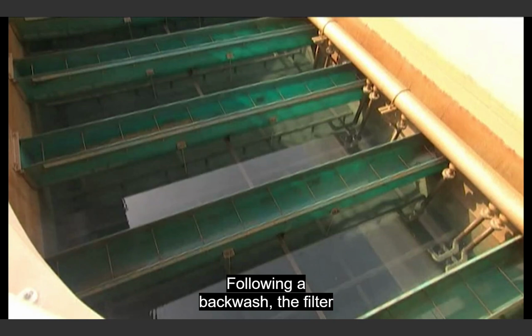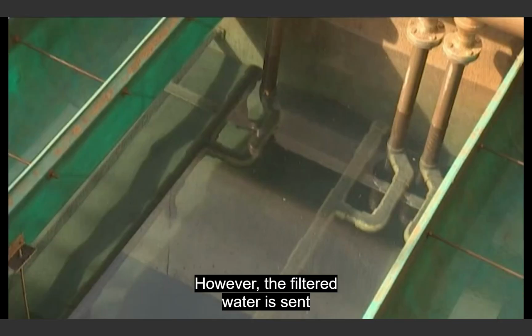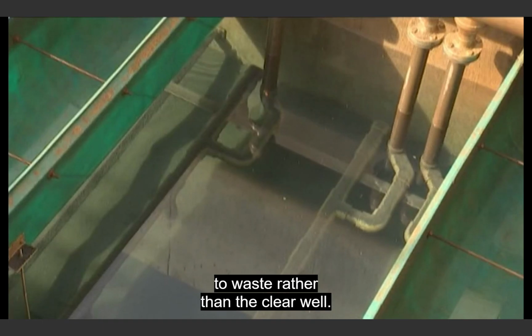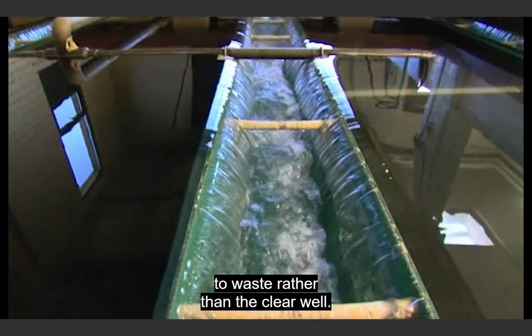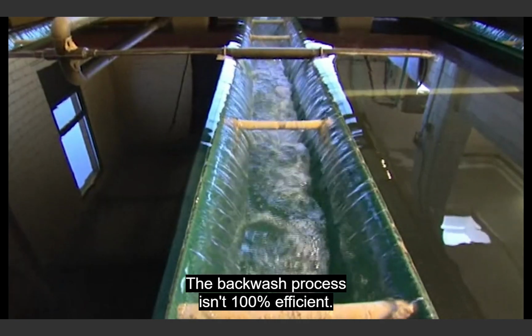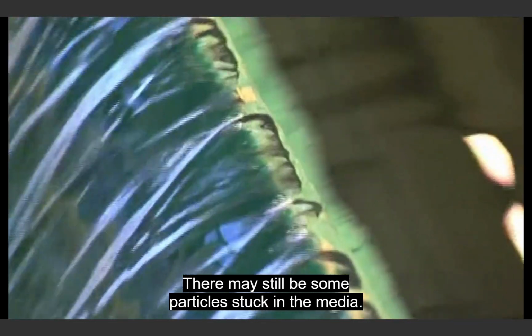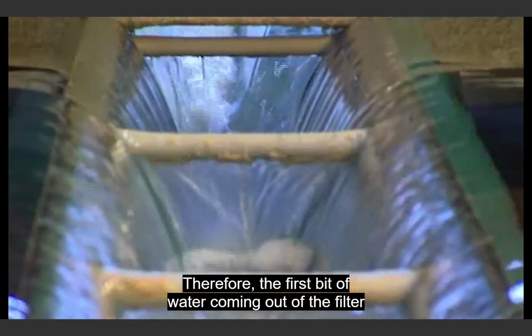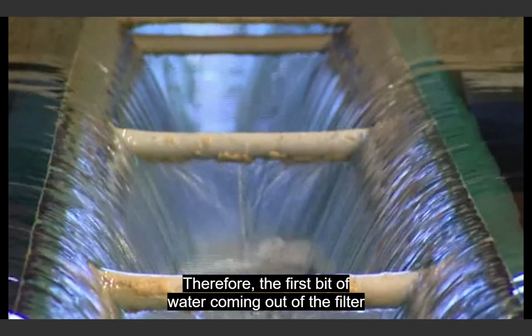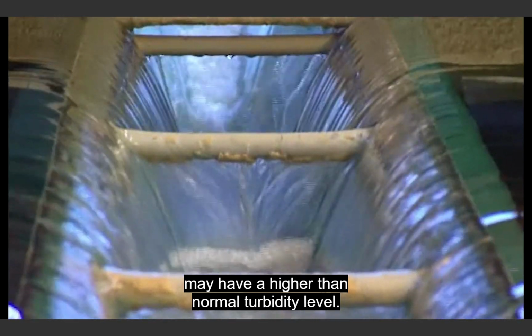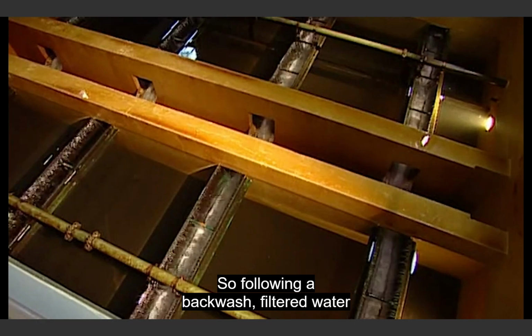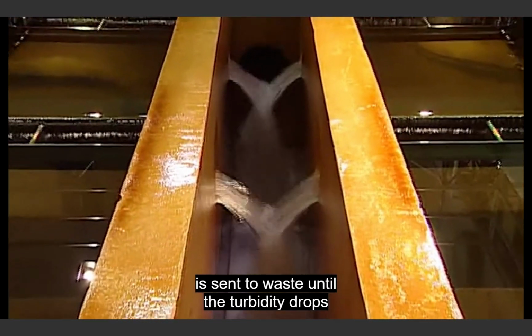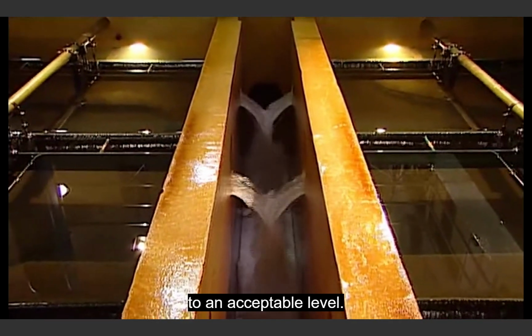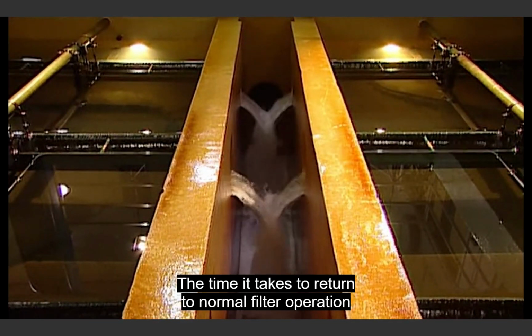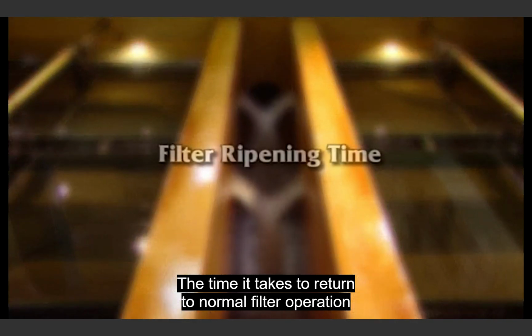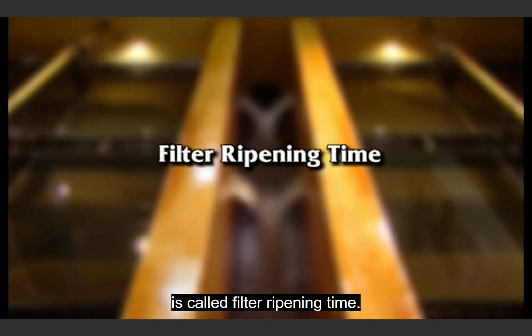Following a backwash, the filter is put back into operation. However, the filtered water is sent to waste rather than the clear well. The backwash process isn't 100% efficient. There may still be some particles stuck in the media. Therefore, the first bit of water coming out of the filter may have a higher than normal turbidity level. So, following a backwash, filtered water is sent to waste until the turbidity drops to an acceptable level. The time it takes to return to normal filter operation is called filter ripening time.